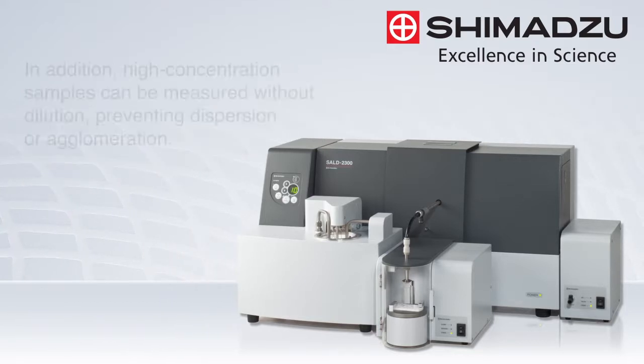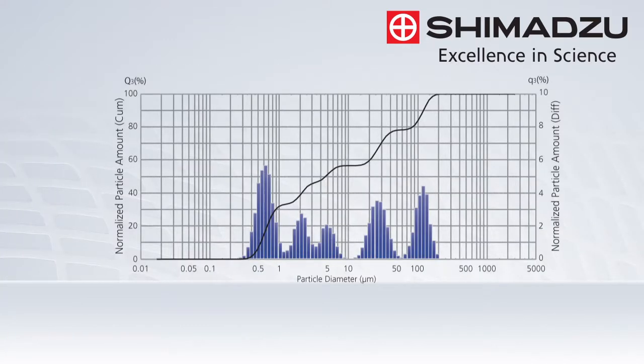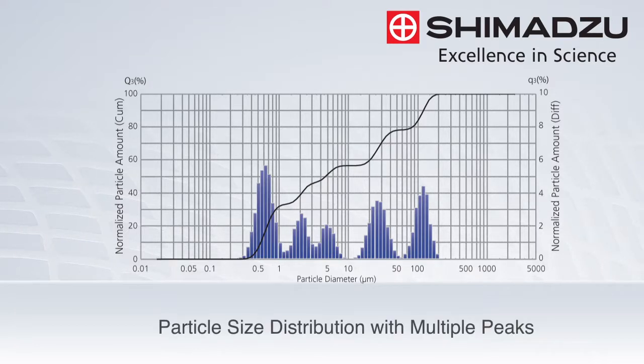In addition, high concentration samples can be measured without dilution, preventing dispersion or agglomeration. Some complex samples may contain several particle size distributions, and with its high-resolution capabilities, the SALD2300 enables the acquisition of data with multiple peaks.